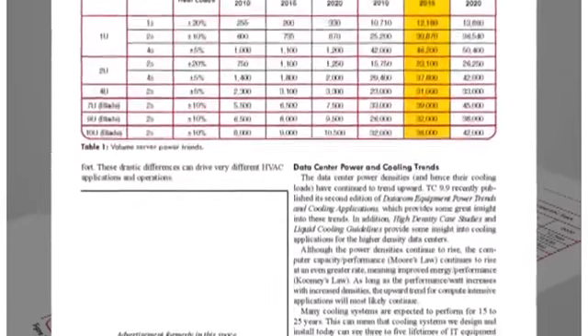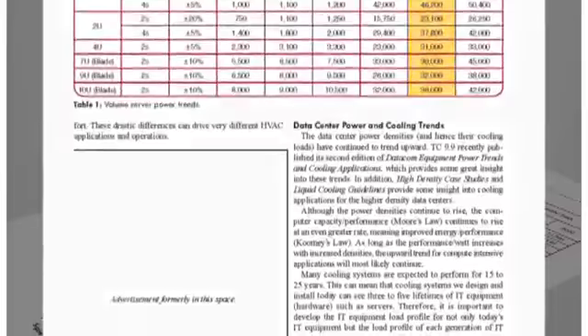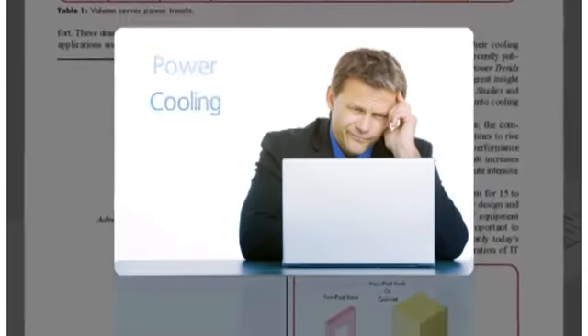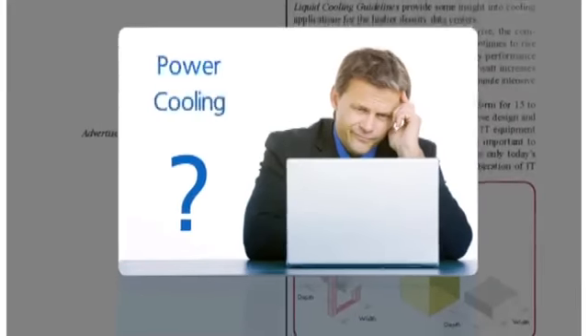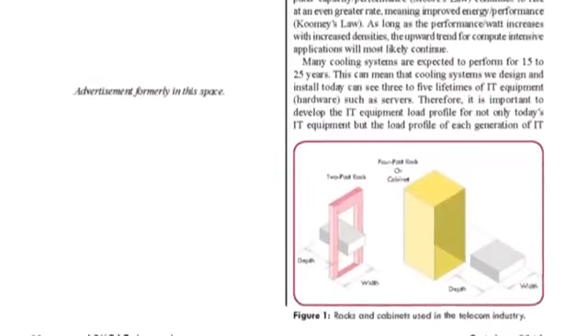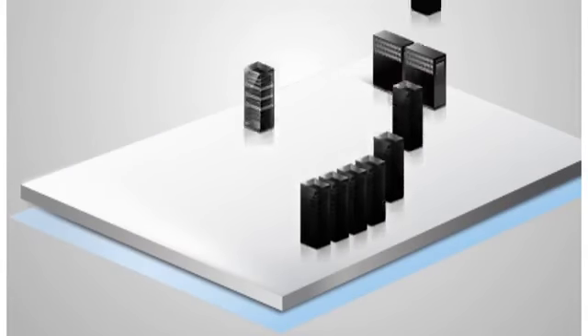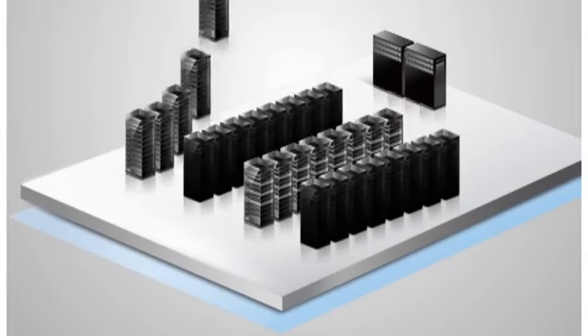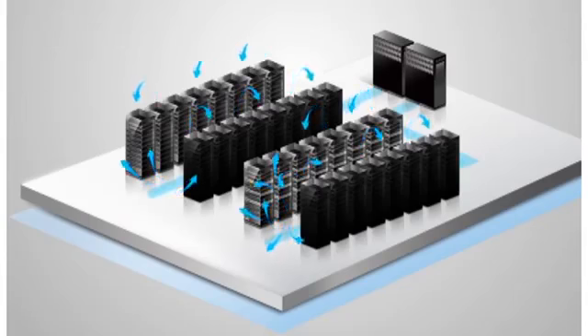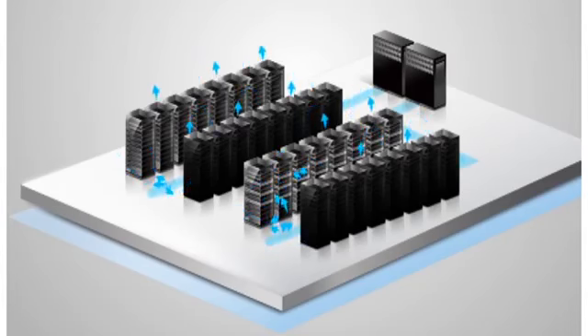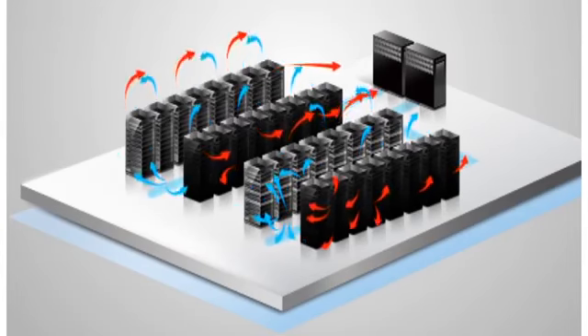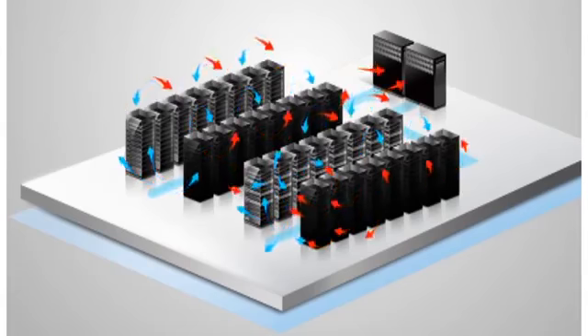This increase will lead IT administrators to pay much closer attention to how energy efficient their power and cooling systems are. Other than the main electrical system, the power and cooling infrastructure has the most substantial impact on the reliability and cost to run a server room. In the past, when power and cooling systems were designed for a data center, they only considered the room's overall heat dissipation. This design involved CRAC/CRAH systems cooling the entire room.